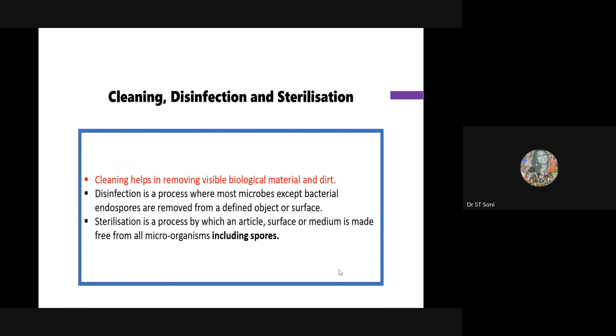Then, importantly, it is removing the biological material or the bioburden from that particular instrument. And we say disinfection kills all the organisms, while sterilization also kills the spores. So importantly, how do we decide which method is to be used in which set of patients? If the patient contact is intact skin, then low level or intermediate level disinfection is okay. If it is mucous membrane or non-intact skin, then high level disinfection is needed, like glutaraldehyde solution, Cidex OPA solution, or I would say even hypochlorite and hydrogen peroxide.